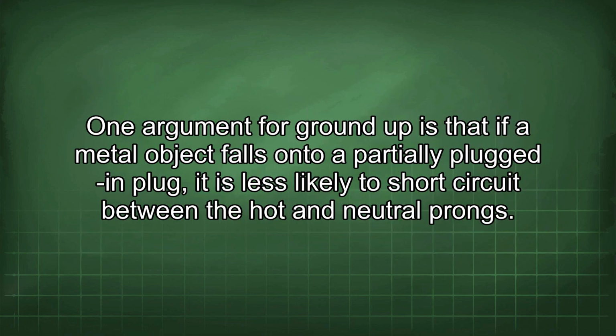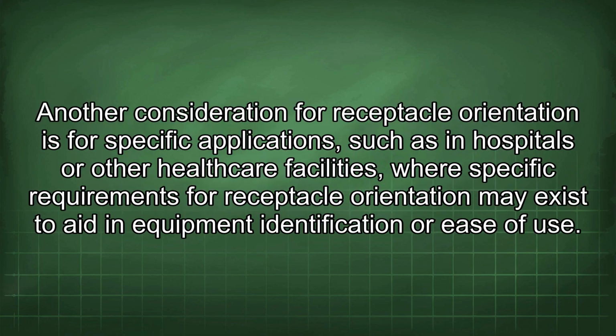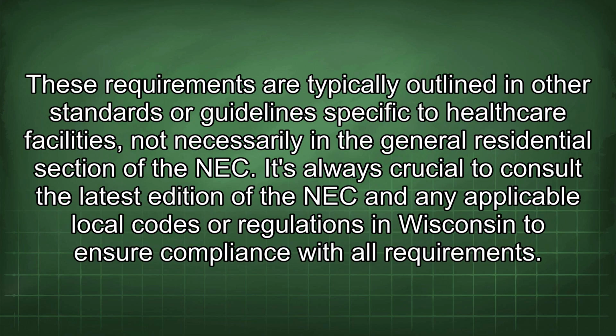One argument for ground up is that if a metal object falls onto a partially plugged-in plug, it is less likely to short circuit between the hot and neutral prongs. Another consideration is for specific applications, such as hospitals or other healthcare facilities, where requirements for receptacle orientation may exist to aid equipment identification or ease of use. These requirements are typically outlined in other standards or guidelines specific to healthcare facilities, not necessarily in the general residential section of the NEC.